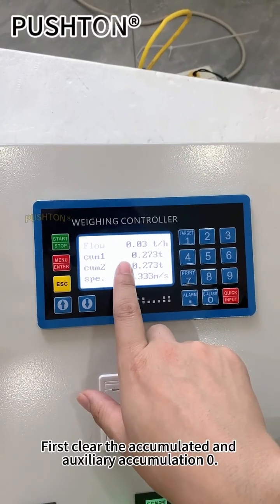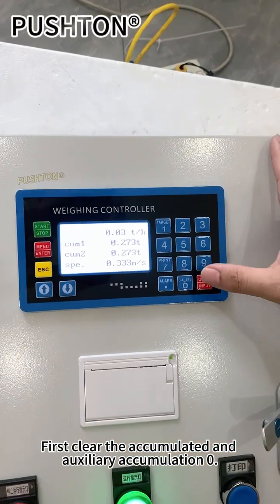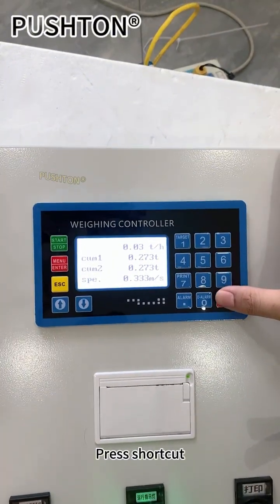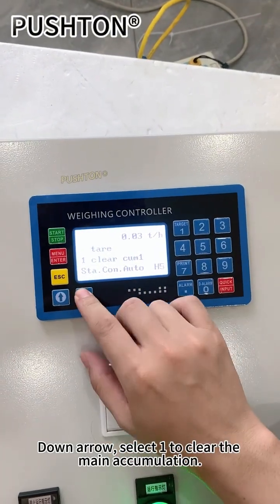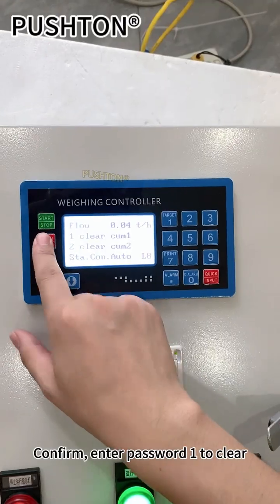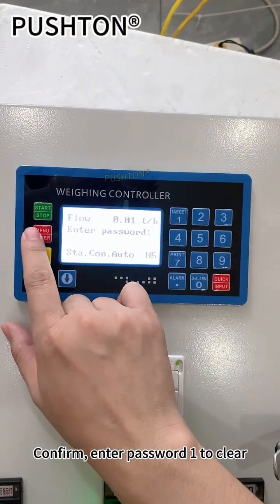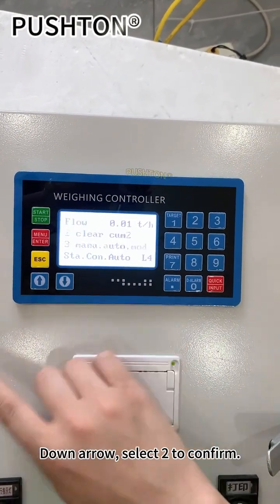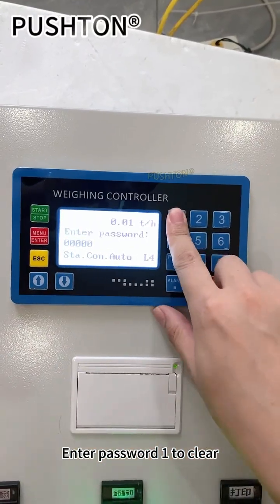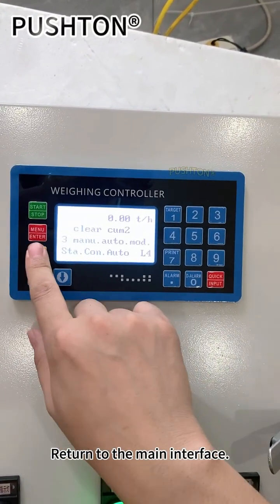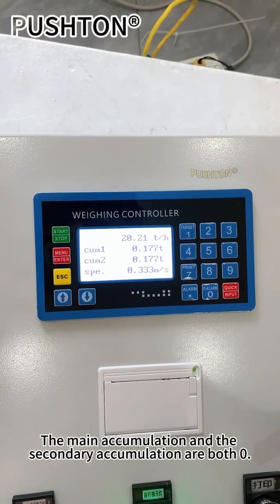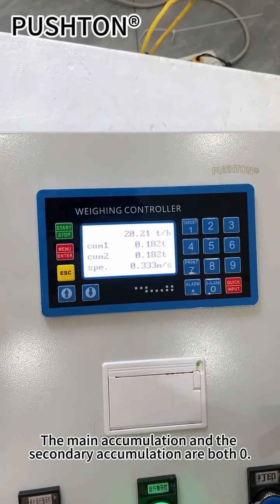First, clear the main accumulation and auxiliary accumulation to 0. Press shortcut. Down arrow. Select 1 to clear the main accumulation. Confirm. Enter password 1 to clear. Down arrow. Select 2 to confirm. Enter password 1 to clear. Return to the main interface. The main accumulation and the secondary accumulation are both 0.